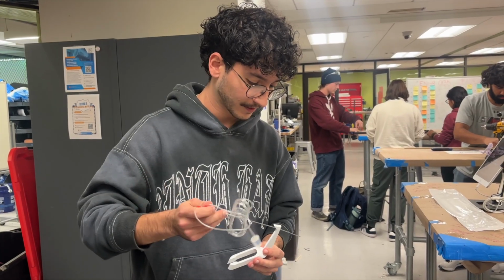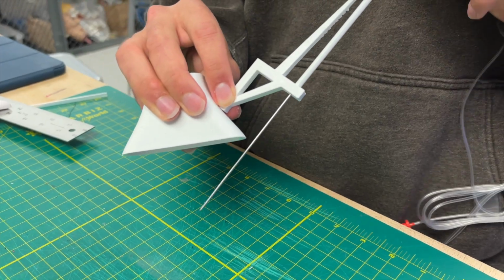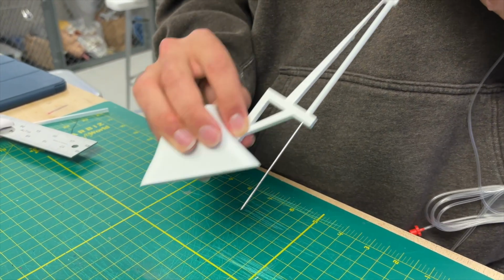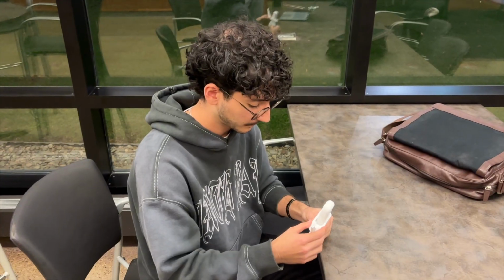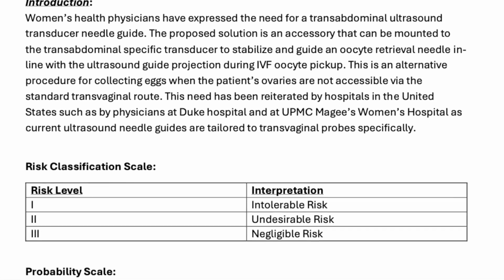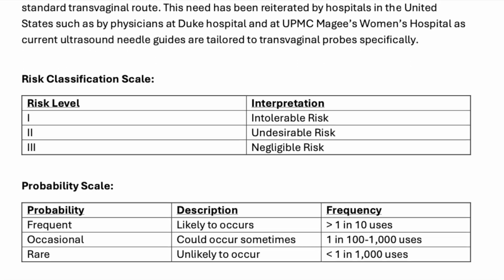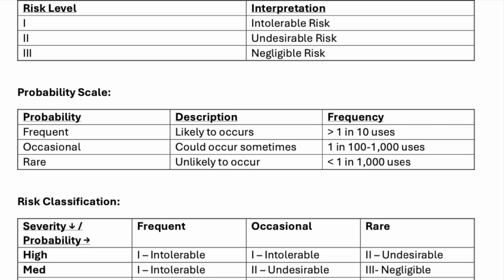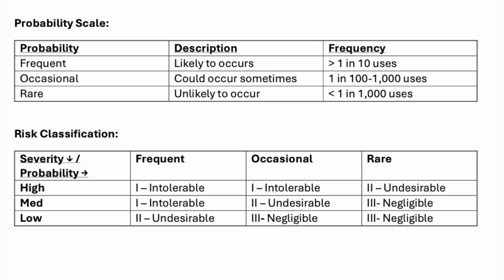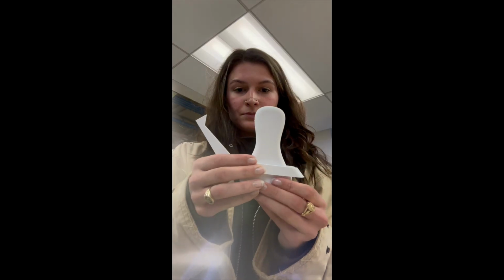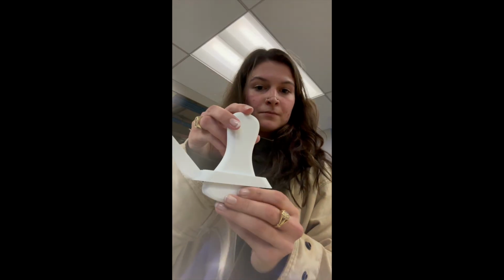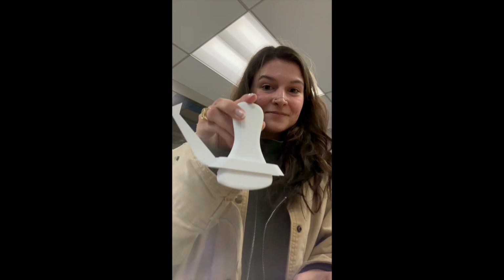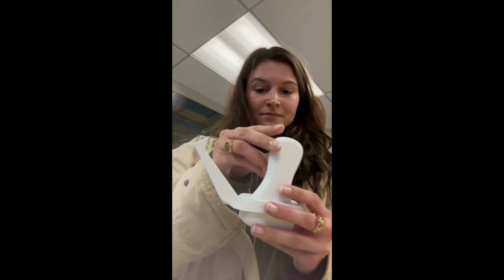As our design developed, we conducted a comprehensive hazard and risk analysis. We evaluated potential failure modes such as improper assembly, mechanical instability, material degradation, and any theoretical risk of electrical shock or interference with the transducer. This analysis allows us to define safety mitigations early, ensuring that the device would be compliant with clinical expectations and reduce user error as much as possible.